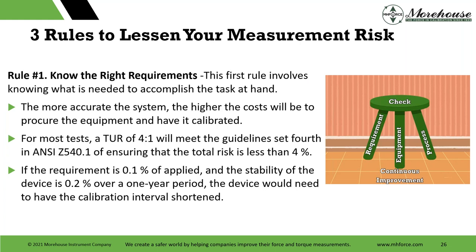Going through rule number one: the more accurate the system, the higher the cost will be to procure the equipment and have it calibrated. There was a fantastic video that talks about what it takes to get to the next decimal place — if today we can read to 0.01, tomorrow we want to be able to resolve 0.001, though that takes a lot more money to improve to that extent. That video is a great one from NIST on that.